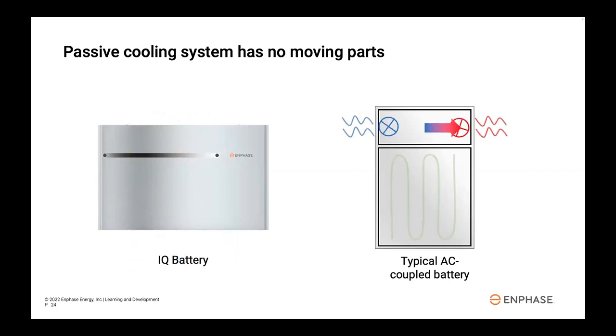Typical AC coupled systems use more common nickel manganese cobalt, or NMC, chemistry, which has an inherently higher susceptibility to thermal runaway and fire. To ensure safe operation, they have active cooling systems that use liquid coolant, a pump to move that coolant through a radiator, and two fans to enable rapid cooling when needed. All these additional moving parts increase the number of fail points in each battery.